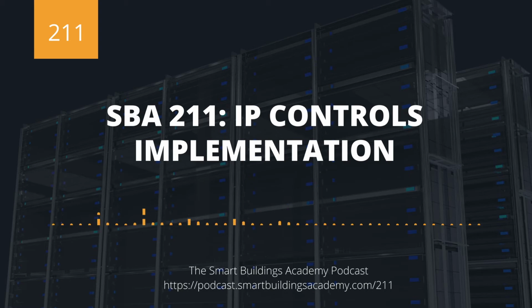Now, with daisy chain, it is the least expensive because you only use one port. Some manufacturers will say limit of 16 devices. Some manufacturers will say no limit on their devices. The reality is you do have a limit between controllers of 100 meters, basically 300 feet, for your traditional Cat 5e or Cat 6 cable. You do have that limitation between controllers. And like with anything, you want to be cognizant of running controllers forever, because the longer you run a daisy chain, the more impact it will have if there's a physical break in the wire.